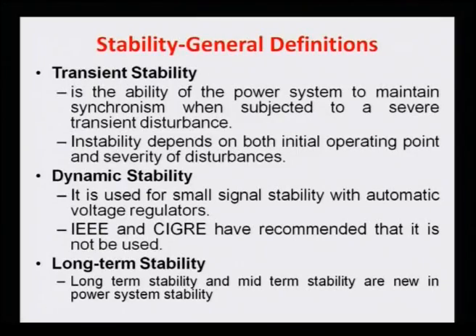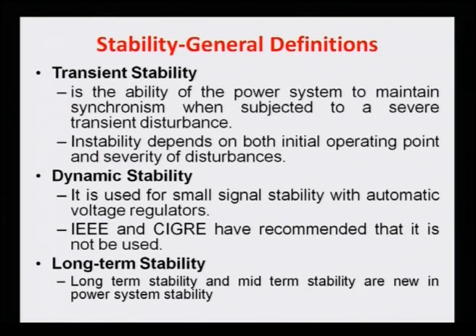Normally, in the broad sense, stability is classified as small signal stability, which we already saw, then transient stability, and sometimes earlier people also used dynamic stability. Now let us see what transient stability is. Transient stability is the ability of the power system to maintain synchronism when subjected to a severe transient disturbance. As I said, small signal stability is related to very small variations or disturbances in the system, but here it is a very severe, sudden, transient disturbance that occurs. Instability depends upon both the operating point and the severity of the disturbance. It is not based only on the type or duration of the disturbance, but also on the initial operating point and the initial condition of the system.